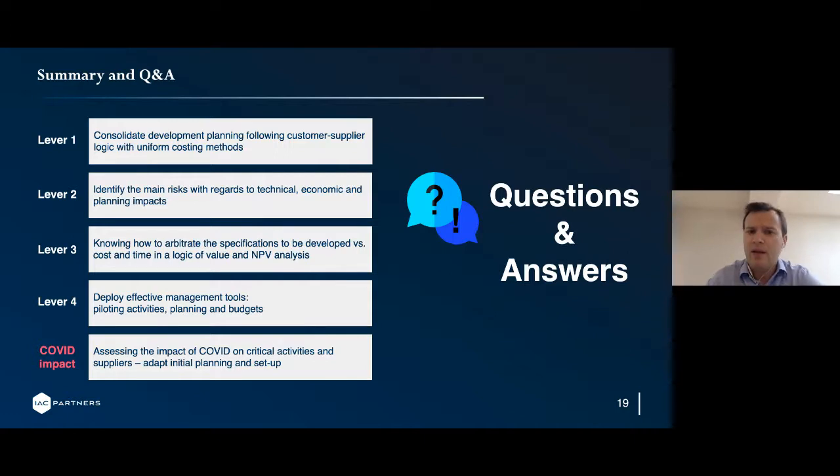Technically, it's true, if both your old and the new product sell the same, with the same volume at the same price. But usually when you develop a new product, it's for a reason. It can be maintaining sales figures, it can be adding features to keep up with the market demand, it could be managing obsolescence. Most of the time, medical devices are developed for 10, 15, 20 years, sometimes on the market, and at some point, some supplies for key components fade away, and you need to re-engineer your product to keep up with that issue. Most of the time, we see that in the electronic boards, for instance. CPUs of 20 years ago are not CPUs available today.